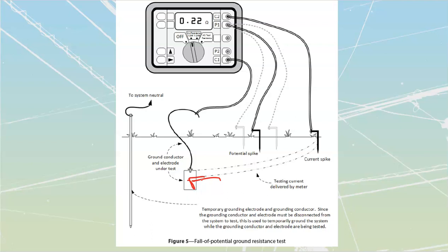If you have areas with high mineral ionizations, ionizing types of minerals, or corrosive minerals, coastal areas with salts are going to be particularly corrosive as well, right? They're all going to cause oxidization. So if we get a really oxidized plate over here, we end up with a lot of R across it. And if we end up with any current traveling through it, a large amount of fault current, particularly high voltage, then I'm going to have a lot of V, right? V is equal to I times R.